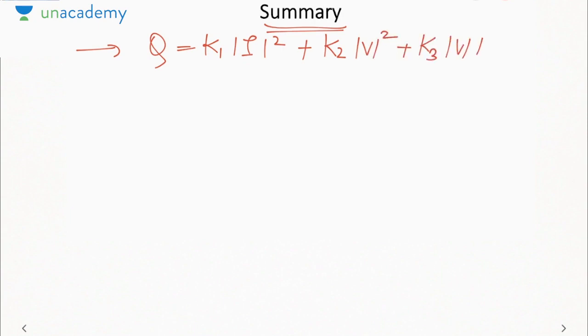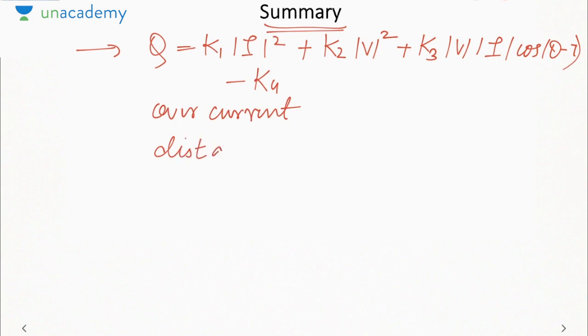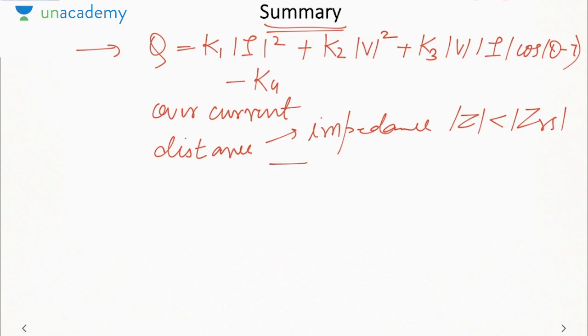So let us summarize what we covered in this lecture. We started with the universal relay torque equation, which stated that torque is mod K1 I square plus K2 mod V square plus K3 mod V mod I cos theta minus tau minus K4. Then we studied on the basis of this what is an overcurrent relay. Then three types of distance relays: impedance, which is used for medium transmission line; then reactance relay; and then Mho relay.